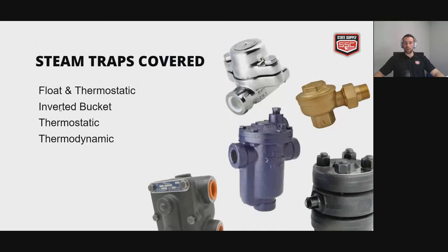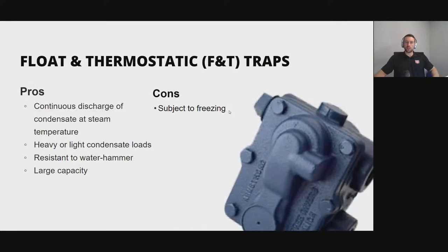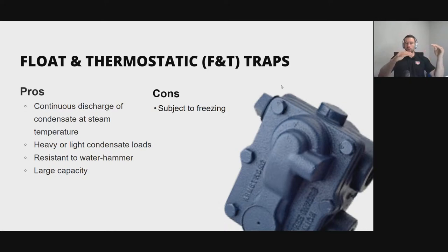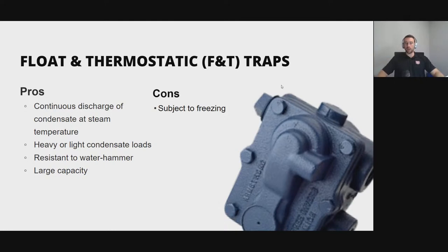The F&T trap has a continuous discharge of condensate — as condensate enters the trap, the ball lifts due to buoyancy and condensate flushes out, so inlet and outlet rates are equal for condensate. These traps can get really large, handling 150 to 200 pounds, and are able to handle a lot of condensate but also work well with a little. They are resistant to water hammer. A con is that they're subject to freezing, but from talking with many people, the F&T trap seems to be the ideal trap for most applications.